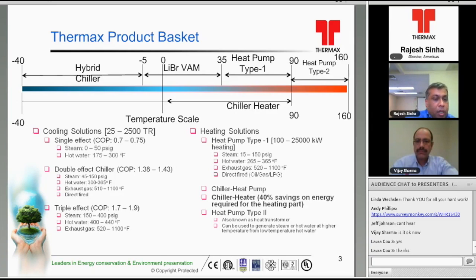The COP is, as written, 1.38 to 1.43, and this could use steam, hot water, exhaust-driven, or direct natural gas or oil-fired. So all the temperature ranges and pressure ranges are right there on your slides. So I'll move on to the triple effect, which again sees another 25% higher investment in terms of initial cost over the double effect absorber, and reduces the energy consumption or the heat consumption by half of what it was in the prior case.